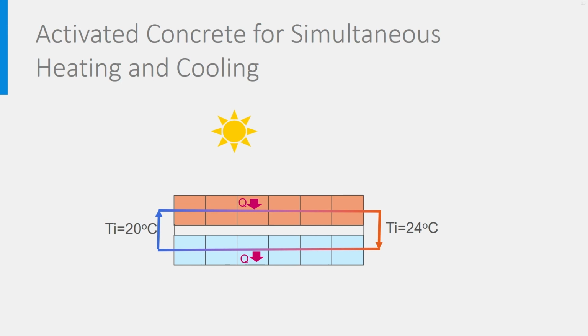The office rooms for teachers have low occupancy and need to be heated a large part of the year in moderate climates, while the classrooms and meeting rooms need to be cooled because of their high occupancy. In such a case, the water in the pipes of the activated concrete is just heated by the hot rooms and cooled by the cold ones in a closed loop, without the use of any heating or cooling generation system.